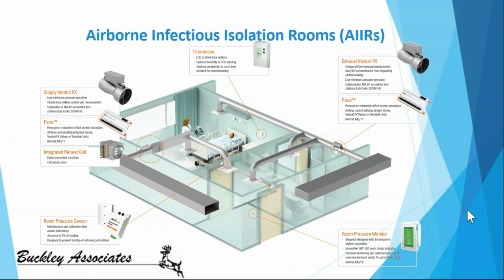Over on the top right side of the image, you can see our exhaust ductwork. We're either going to be pulling out, this can either be exhaust or return. This can go up to a lab exhaust fan or high plume fans, or these can be recirculated if we have the right type of filtration. Over on the left side here, we just have supply. Here we see a valve and some reheat coils, but really what we're doing is pressurizing the space with the supply air over here.